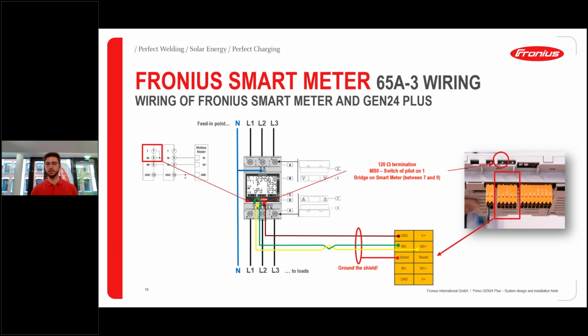And usually what we recommend is to use a Cat5 Ethernet cable at minimum, or a higher category like Cat6. Cat7 can also be used. However, there are a few important things that you need to remember. If you use a cable, use one which is shielded. So that's why we say Cat5 at minimum. A shielded cable, ground the shield on one side. Also very important to ensure the best quality of our data.